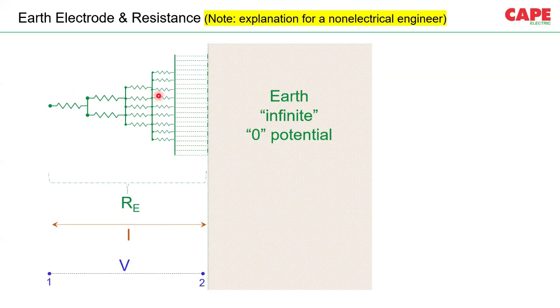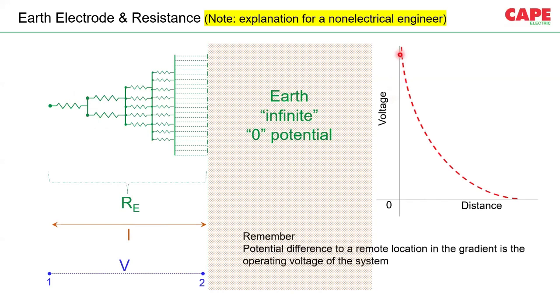And the voltage gradient is across these 2 points. Here on the right side, you can see the voltage gradient. Voltage gradient means between point number 1 and 2, there is a voltage that exists during the fault. Remember, this voltage gradient, or this potential difference to a remote location in the gradient, is the operating voltage of the system. The fault voltage, the maximum, the peak of this voltage, is the maximum operating voltage of the system. Let's say your fault is 230 volts, then the peak of the gradient is 230.